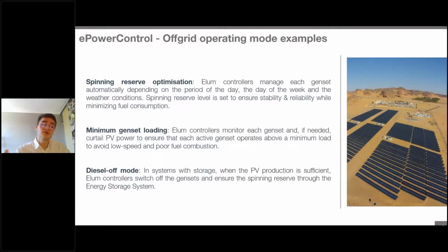But also still to ensure that we have this minimum genset loading on the genset side, which is really key for the safety of the plant and to ensure that you can use those gensets in this off-grid configuration. The Elum product e-power control is also able to manage diesel gensets, turning them on or off according to the site configuration and the load current demand.